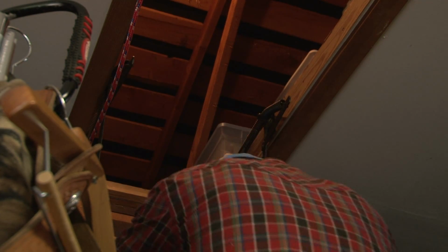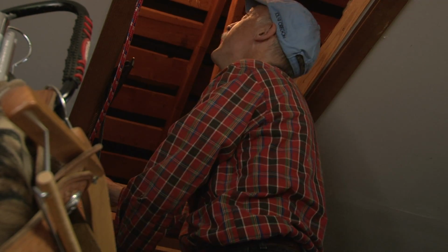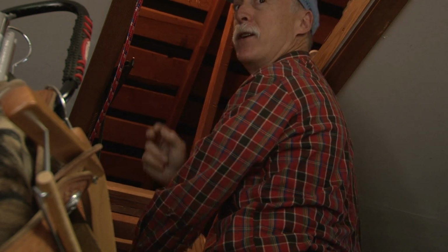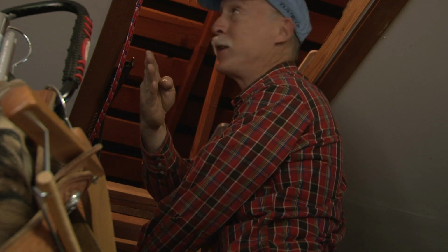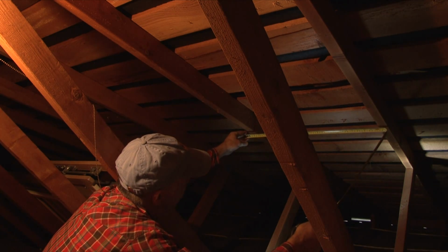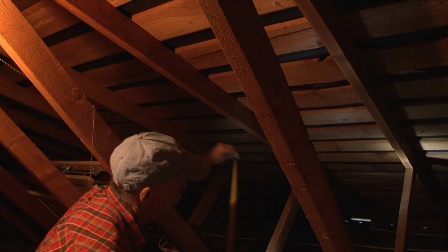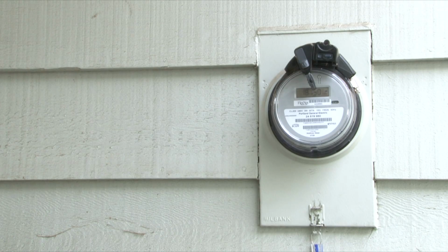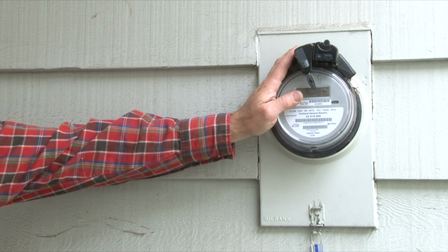Moving from the roof, the technician checks the attic for access and assesses the capacity of the structural members to support the dead weight of the solar panels, which can weigh between 3 to 4 pounds per square foot. The load is generally not a problem for roofs which meet current building codes, though older homes sometimes require an engineering analysis. Next, the technician needs to inspect the electrical services.